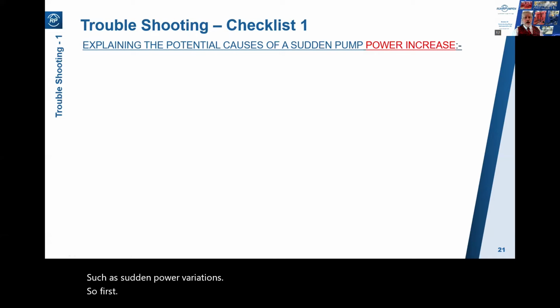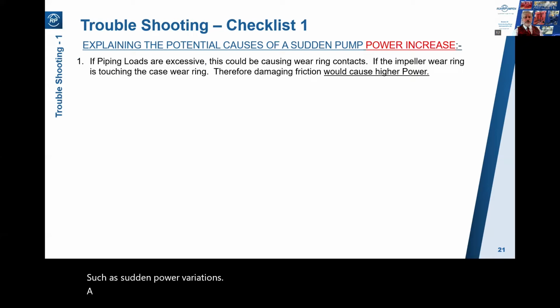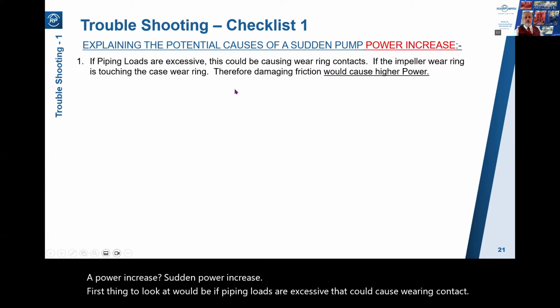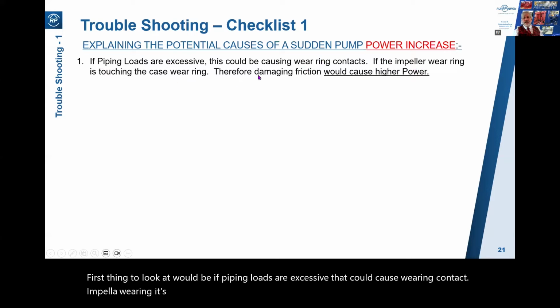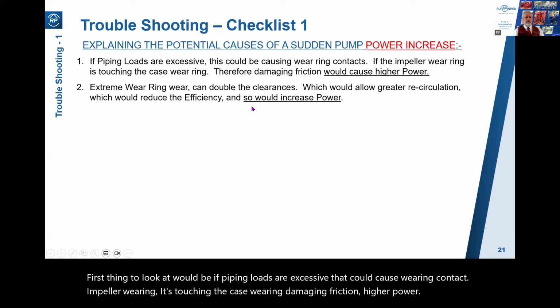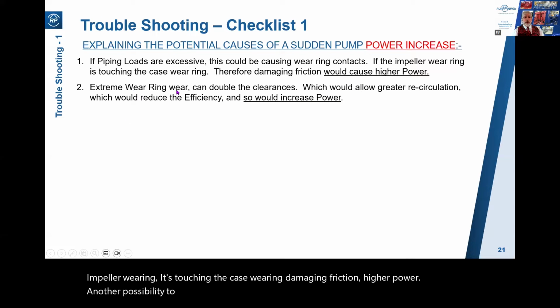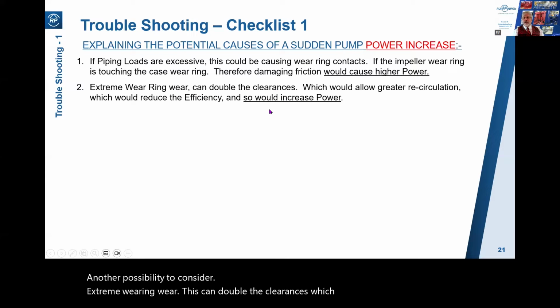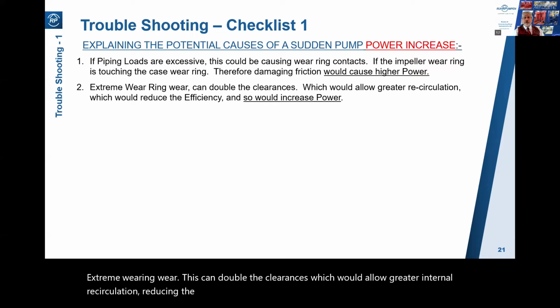So first, a sudden power increase. First thing to look at would be if piping loads are excessive. That could cause wearing contact, with the impeller wearing ring touching the case wearing ring, damaging friction, higher power. Another possibility to consider is extreme wear ring wear. This can double the clearances, which would allow greater internal recirculation, reducing the efficiency, so you get an increase in power.